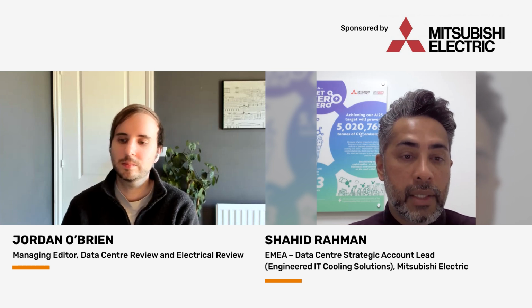This recovered heat can reduce the load on the boilers and supply heating for offices, washrooms, showers, etc. Other benefits - if it's a new build or new project planned without a gas connection, that helps energy efficiency and sustainability. But for the data center itself, having a dedicated water source heat pump using the condenser water, or alternative water from the data center cooling system, as its energy source is a really good approach for large water-cooled chiller applications. It improves the larger capacity of the chillers, the plant side, and the return on investment and capital expenditure. It's really good when you can introduce these technologies.